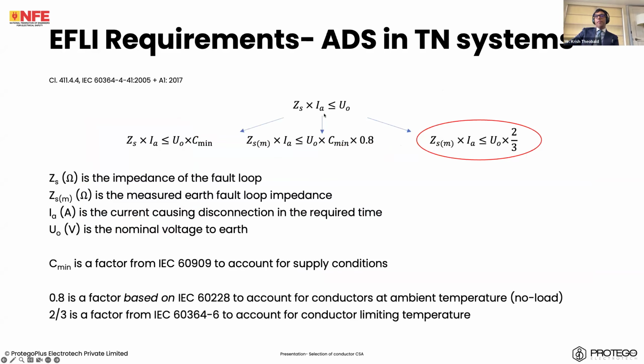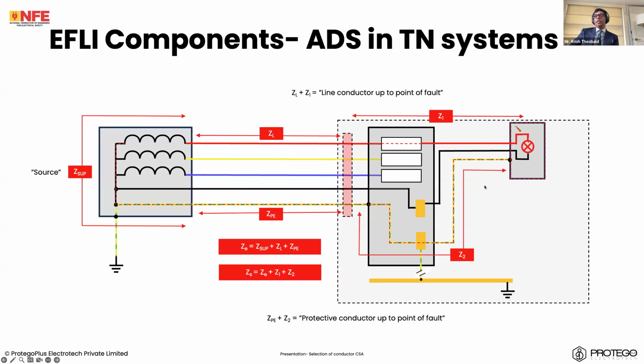So IA is 30, U0 is 230. So 230 divided by 30 is 7.67 ohms. Multiply that by a two-third factor, and we get 5.1 ohms. I'll give you a better example. If this was, say, a 100 amp device where disconnection was happening at times 10, 1000 amps, 230 volts divided by 1000 amps is 0.23 ohms. And we apply a two-third correction factor, which becomes 0.153 ohms.